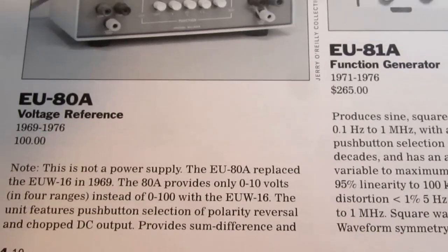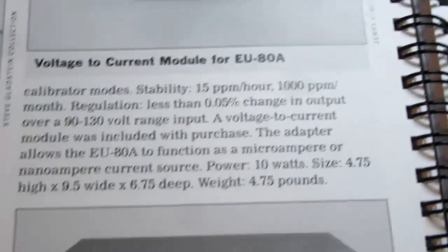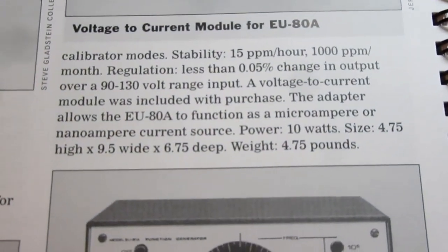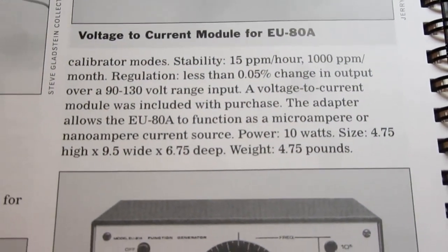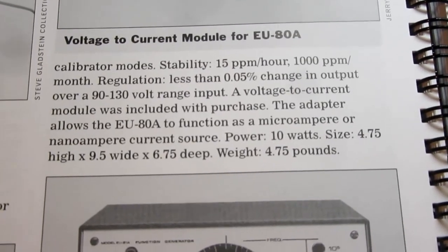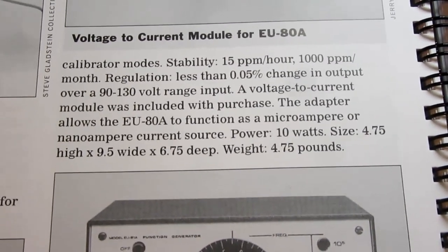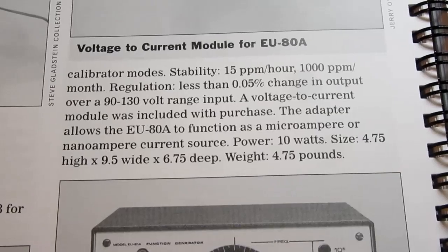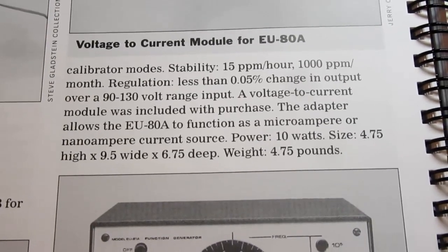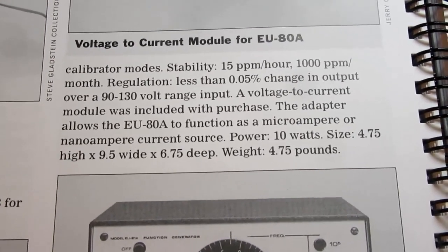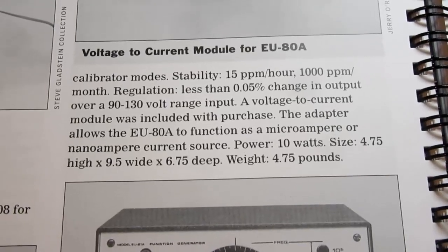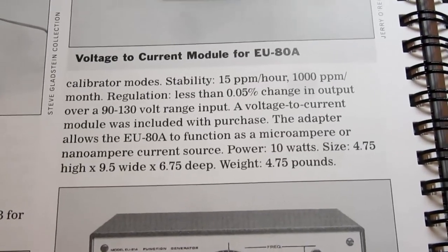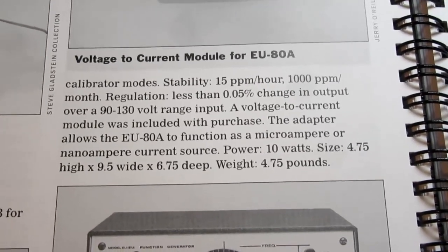It provides sum and difference and calibrator modes. Its stability is 15 ppm per hour, that's parts per million per hour, 1,000 parts per million per month. The regulation gives you less than 0.05% change in output over a 90 to 130 volt power supply range.